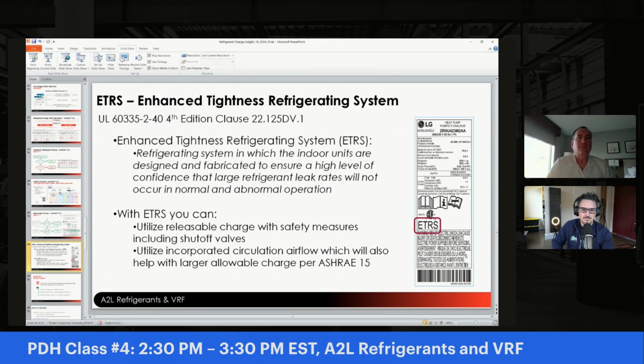This is a new concept released in the fourth edition of the UL standard, called ETRS, or Enhanced Tightness Refrigerating System. This designation means the system has indoor units made to a higher level of confidence that large refrigerant leaks will not occur in normal and abnormal operation. With the ETRS designation, you can utilize releasable charge with safety measures, including valves, and also incorporate airflow. Our nameplates will actually have an ETRS designation signifying what the equipment is designed for.